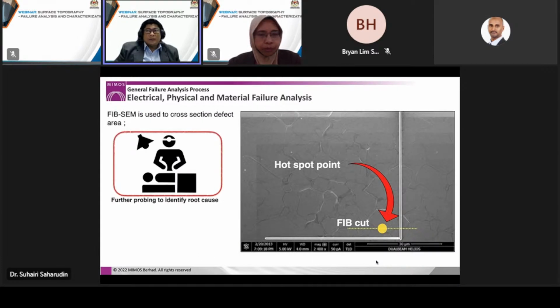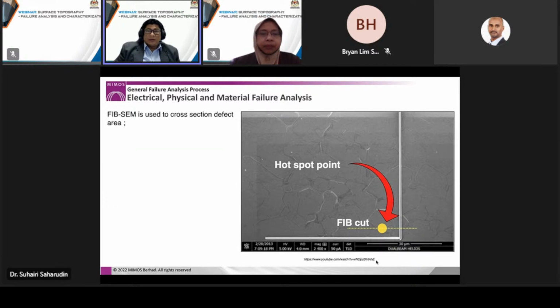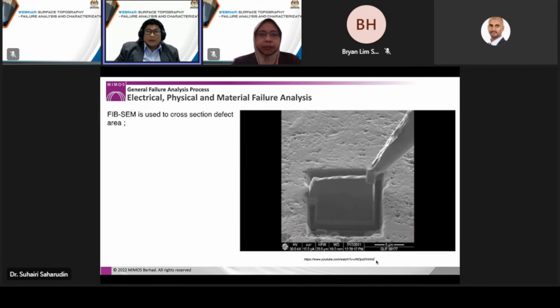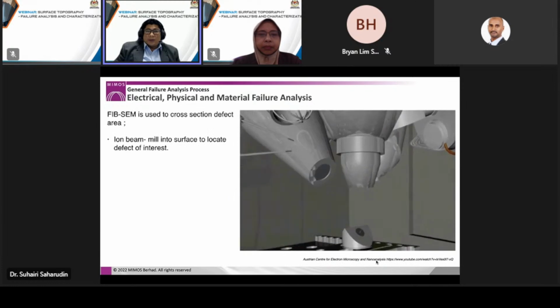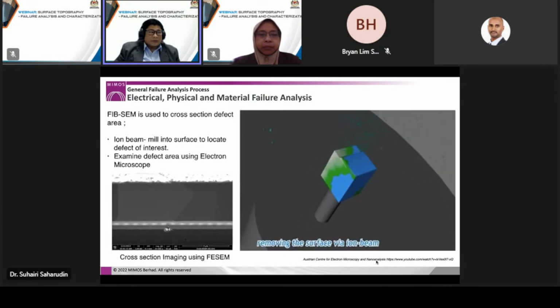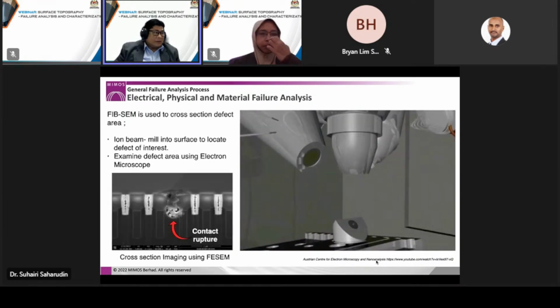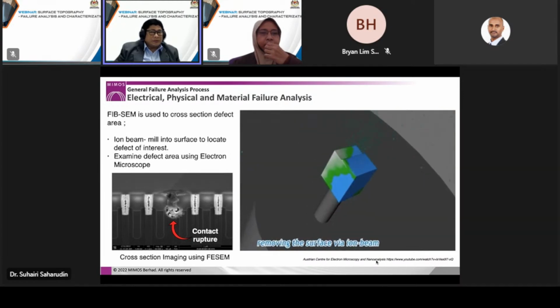Of course, the fault isolation result will be just an image without much information in it if no action is taken upon it. So the decision of whether you have to go to the operation theater depends very much on the nature of the investigation. In this case, once we get permission from our customer, we will perform the next level of diagnostic. For example, we can perform a FIB cut to create shapes known as lamella, using a focused ion beam to etch or mill a specific area in the specimen. The prepared lamella can then be analyzed further by electron microscope, in this case to reveal contact rupture at the localized area, which indicates a possible cause of a short circuit.